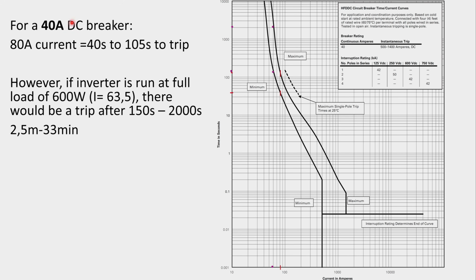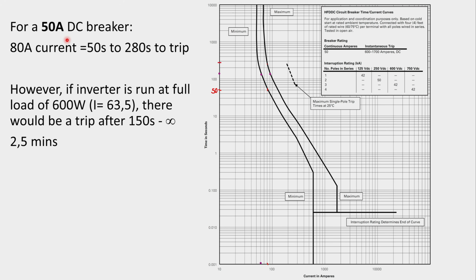If I choose a 40 amp circuit breaker, this would work if I'm protecting for overload. Now this depends on your selectivity. If you're worried about the inverter, if it's not a good quality inverter, or if it hasn't got good cooling, or if you're worried that the user might damage it, well, yeah, maybe you could use a 40 amp circuit breaker. So for this application, I'm just going to use a 50 amp DC breaker. And the reason is because the inverter already has its own internal protection. I don't want the circuit breaker to trip before the inverter trips. The inverter must cut off the supply as it's designed to do. It is a good inverter, so I'm confident in that.